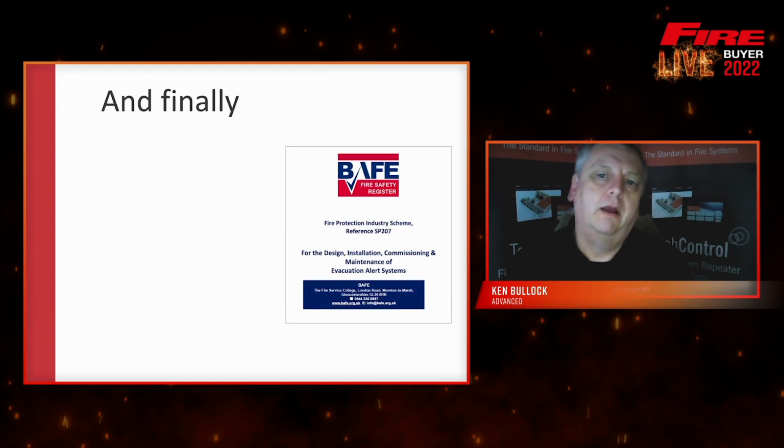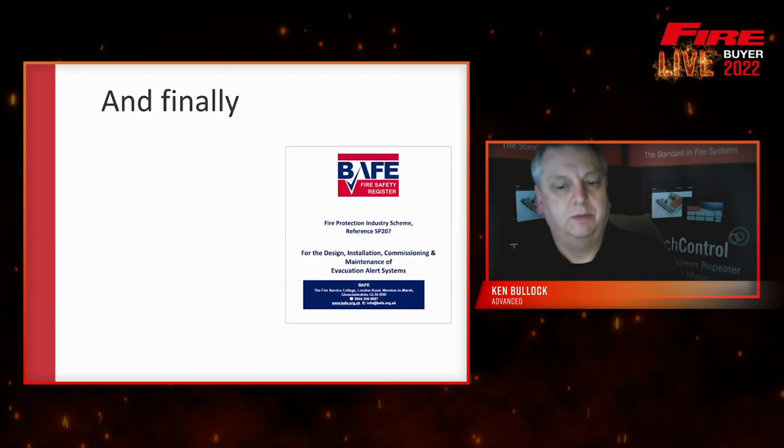Finally, from me, really a look at third-party accreditation, purely because third-party accreditation is something that, as an industry, we're driving towards. BAFE operate most of the third-party schemes for the fire detection and alarm industry. They recognise that evacuation alert systems are not the same, and therefore they have produced SP207 for that particular application. So we have BAFE SP207 as a third-party accredited scheme for all elements of an evacuation alert system.